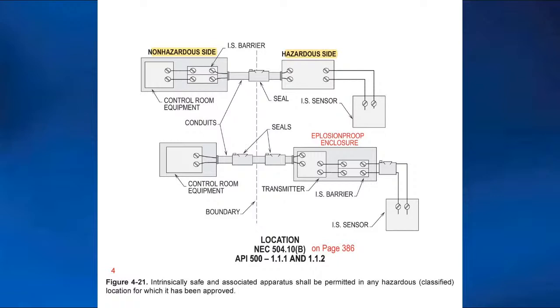But if you put that enclosure in the hazardous location, to the right where you see the red, then that's going to be an explosion-proof enclosure. You have to seal within 18 inches of the enclosure, seal at the boundary, and then you've got to seal on that other side to those high-pressure sensors that you might have there. So it's very important where you put the enclosure that houses the barrier. That's the location in 504.10(B), and then you have the API there also.